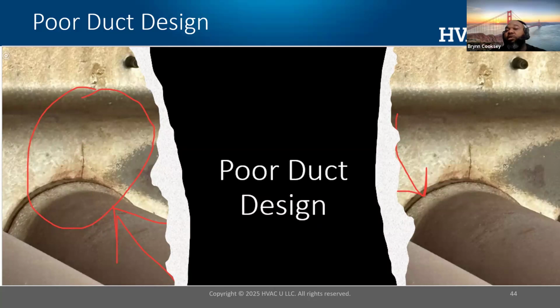So again, if you don't do your due diligence on a design and you put a heat pump in, no, you're not going to have a combustion related failure, but you may damage the compressor or the main part of the heat pump outside.